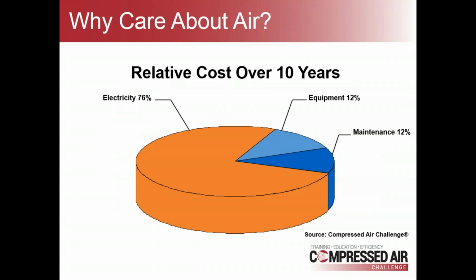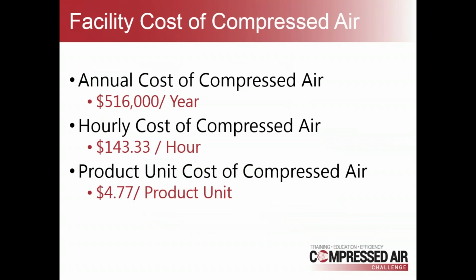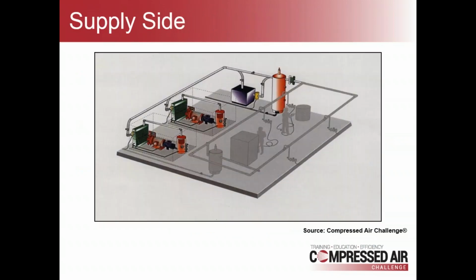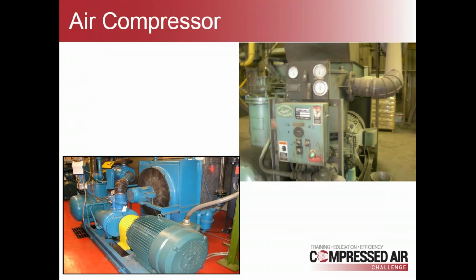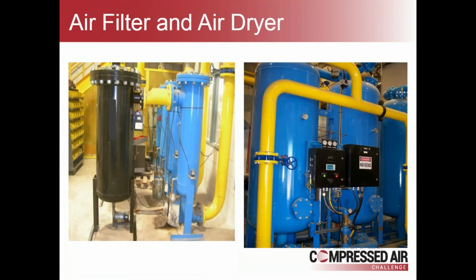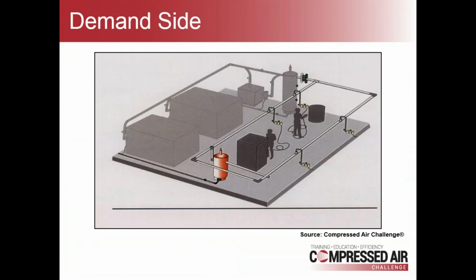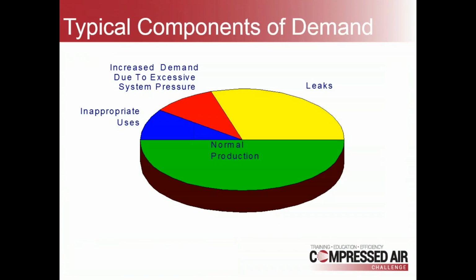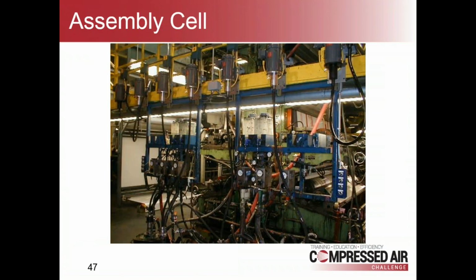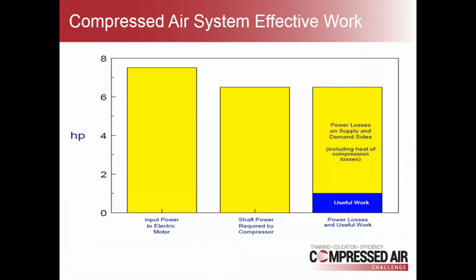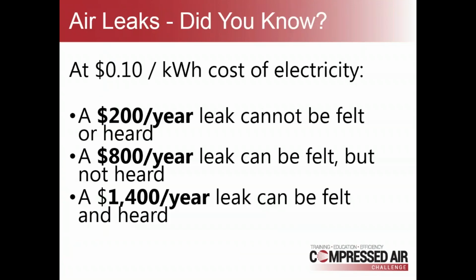So you go over the cost of what it is over 10 years. You can see electricity is the major cost of it. It defines some of the metrics and puts it in the facility cost, so they know how much their actual cost is, what the hourly cost is, and what their production per unit cost is. It talks about what the system is and reviews the supply side, showing pictures of their air compressors, their filter dryers, their receiver tanks, and the demand side, the typical components of demand, what there is in their actual plant. You can put in all different types of it, the effectiveness and efficiency of the system, how leaks are, and what the leak costs are.